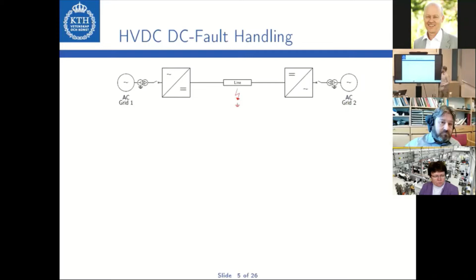The thing is, as in every power system, faults can also appear in an HVDC system. In an HVDC system, the faults can appear on the AC side or on the DC side, and the handling of DC faults is particularly challenging. In this picture, you can see a point-to-point HVDC link consisting of two converters. These two converters are interlinked by a transmission line. Let's say a DC fault appears right on the DC link.